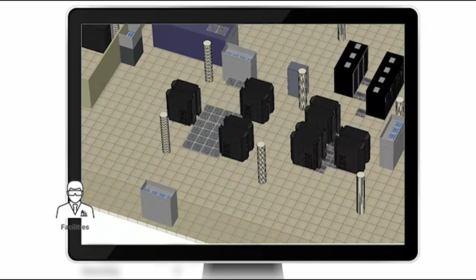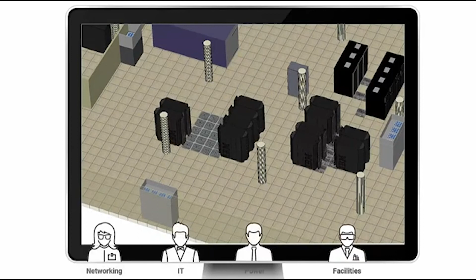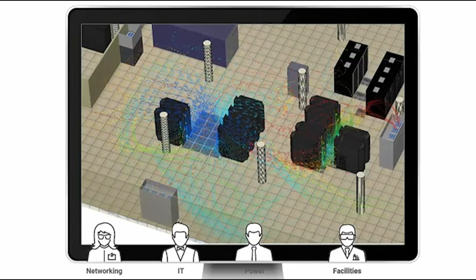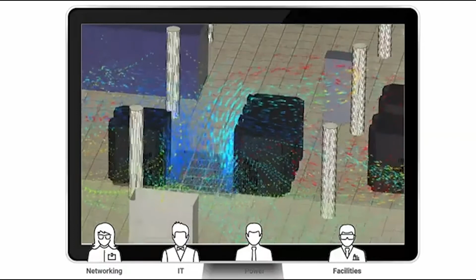Using the simulation, they are successfully able to reduce the wasted airflow and remove the additional cooling unit that they placed earlier, resulting in energy and money savings that they wouldn't have had if they hadn't simulated first. They've also recovered that 30 kilowatts of capacity that would have originally been lost if they'd installed without simulating it in the digital twin first.